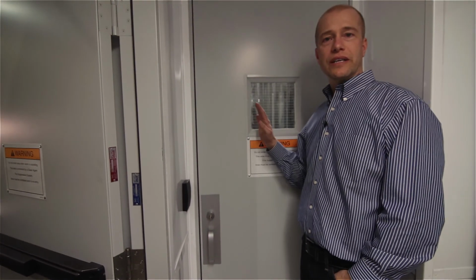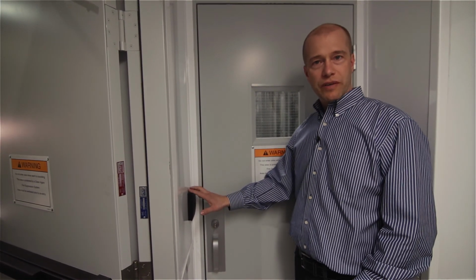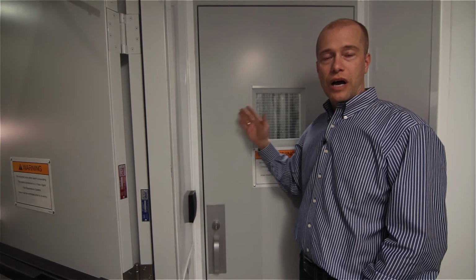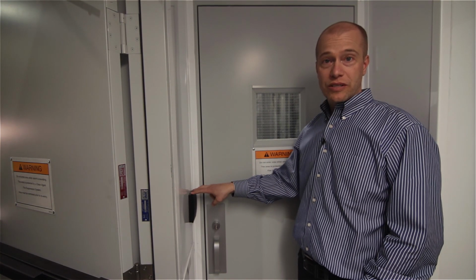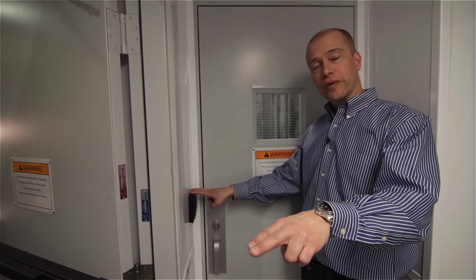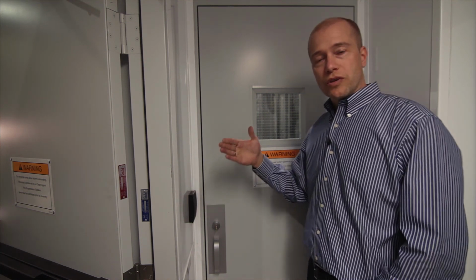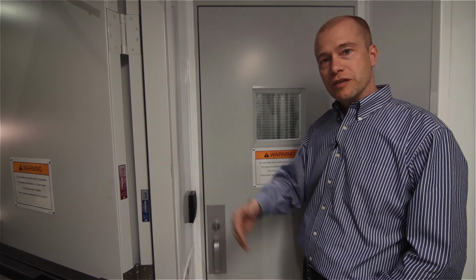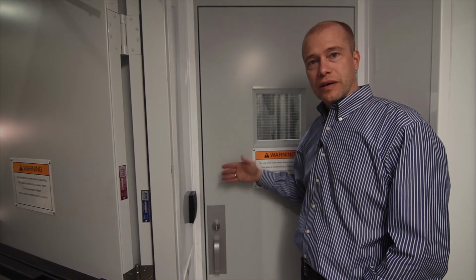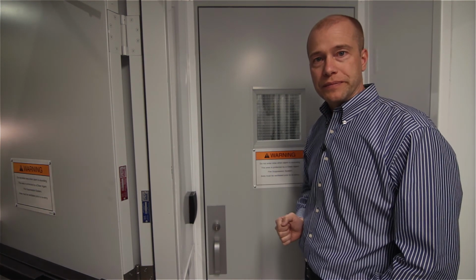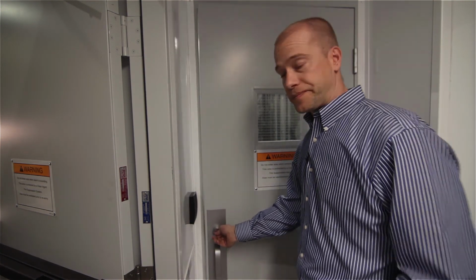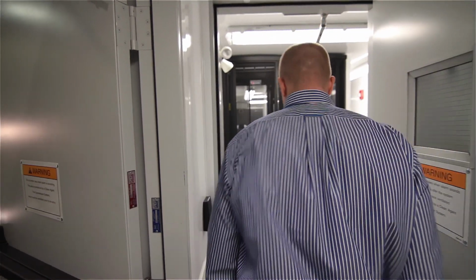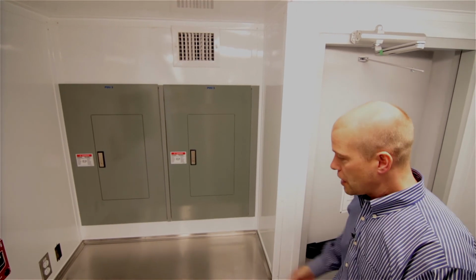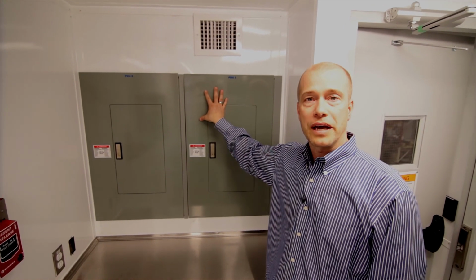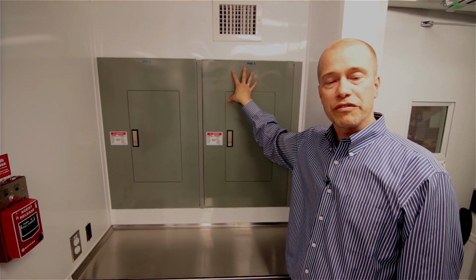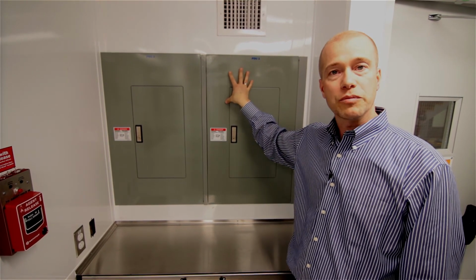So zone 3 is the data center itself. And as you see, we have a card access control reader here for our highest security zone. And what this actually allows us to do is link it with the other card reader on the outside of the vestibule. So there's no way that the door will be open to the vestibule and the door open to the data center. The 2 card readers will stop that from happening. So let's go have a look. We're in zone 3 in the data center. And the first thing I'm going to talk about are the PDU panels. There's independent PDUs, one for each side, attached to independent UPSs.